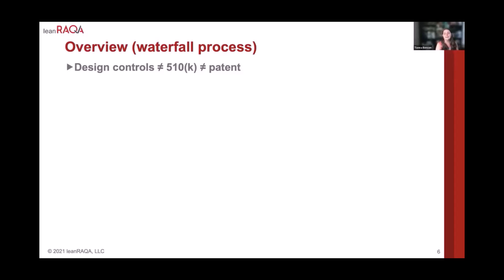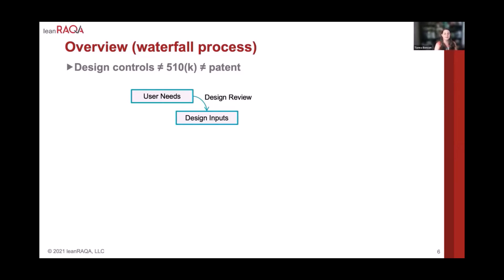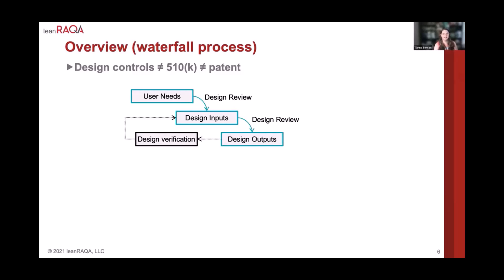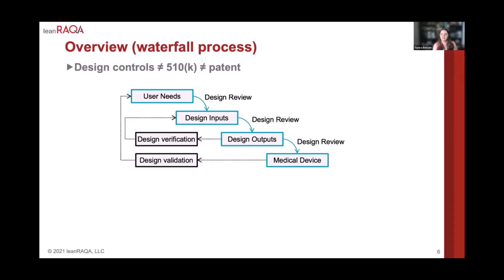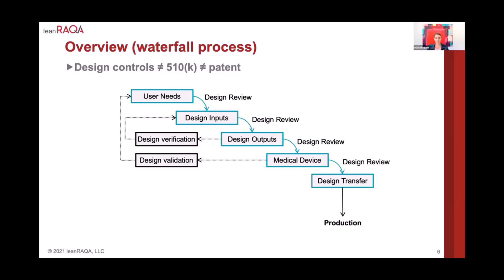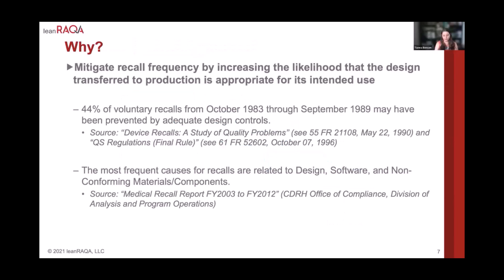We always see what's kind of a traditional waterfall process, but what we don't see is what design controls are not — they're not your 510(k), they don't mean that you have market clearance, they're not your patent. It's a process with a bunch of documentation as outputs. It starts with user needs, which feed into design inputs, and those inputs feed design outputs. You verify that your outputs are meeting your inputs, you get a medical device, you validate that device meets your user needs — that you actually built the right device — and then you go through design transfer and get to manufacturing and mass market production. That's the traditional process, but there are a whole bunch of steps. It's a huge series of processes and the culmination of a lot of effort.